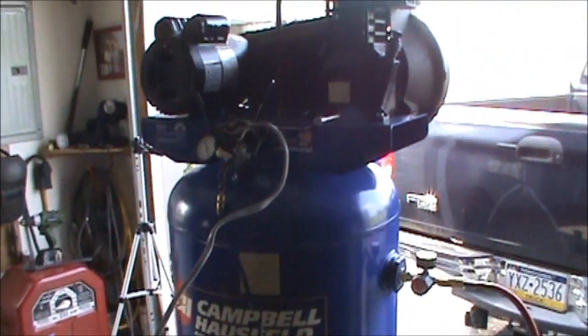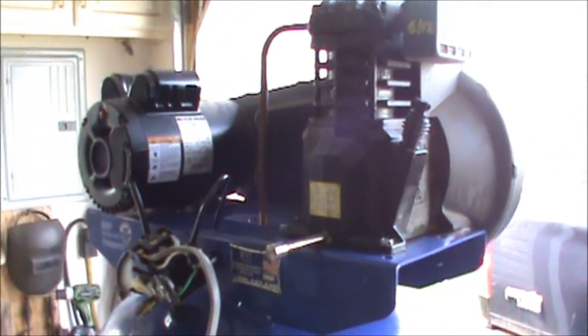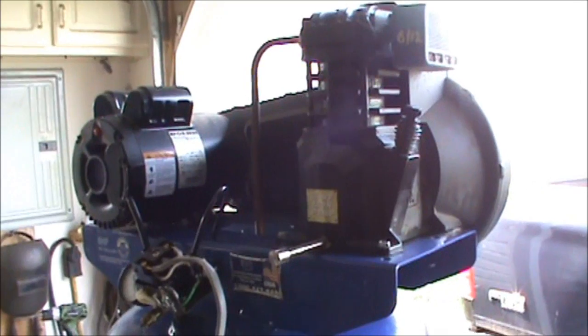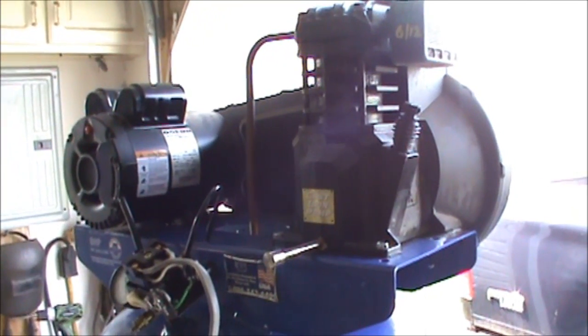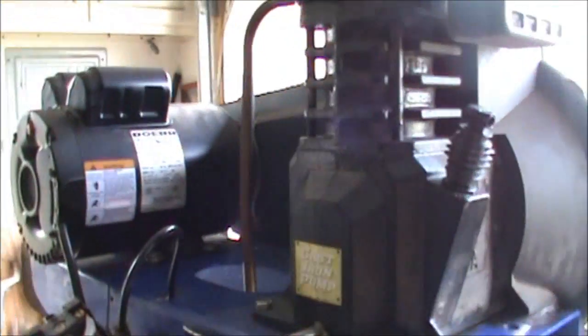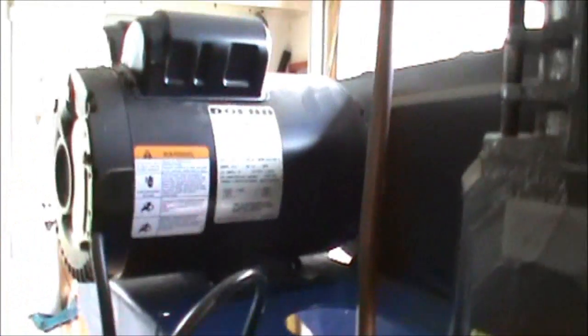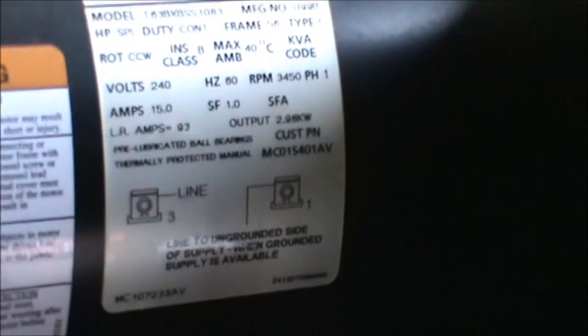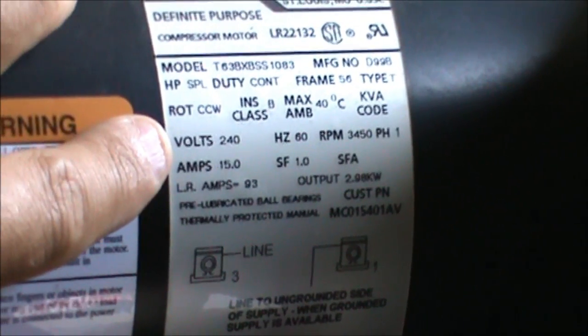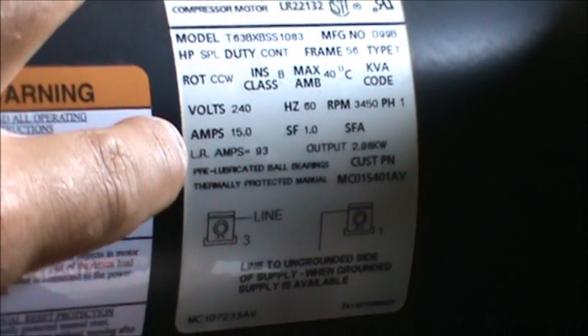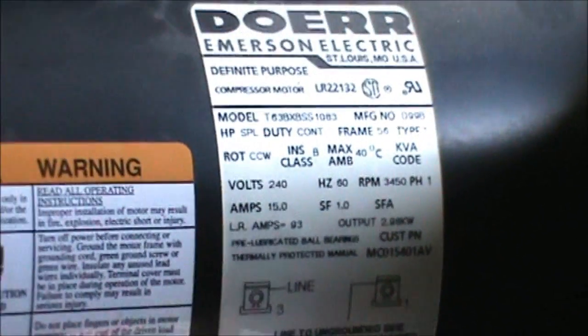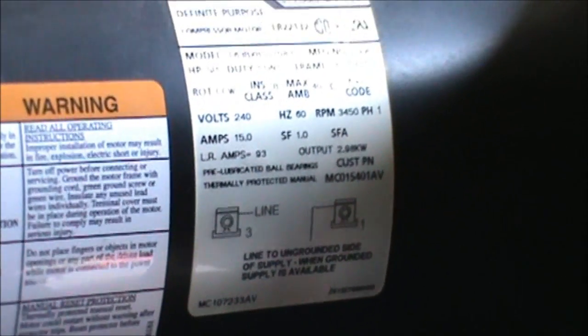How's it going guys, this is Double Wide Six and I'm bringing a video today on how to hook up a circuit breaker to a 240 volt appliance. So as you can see, I got an air compressor I picked up the other night. If we take a look at the motor, the important thing you want to look at here is the volts - this is 240 volts and the amps are 15. So what we're going to do is hook it up to a breaker, make sure that it has 240 volts, and we're going to have a 20 amp double breaker. We'll show you how to wire that up at our service panel.